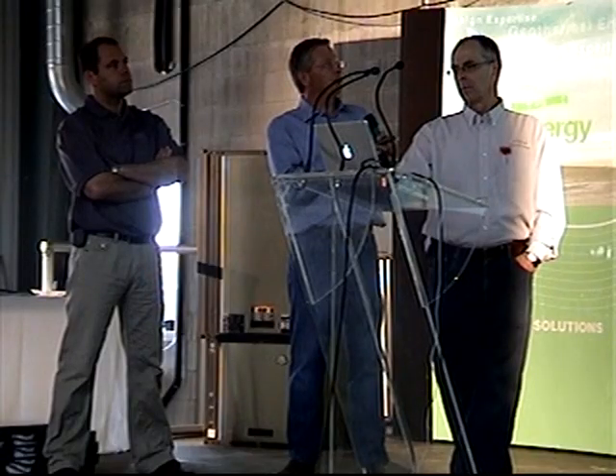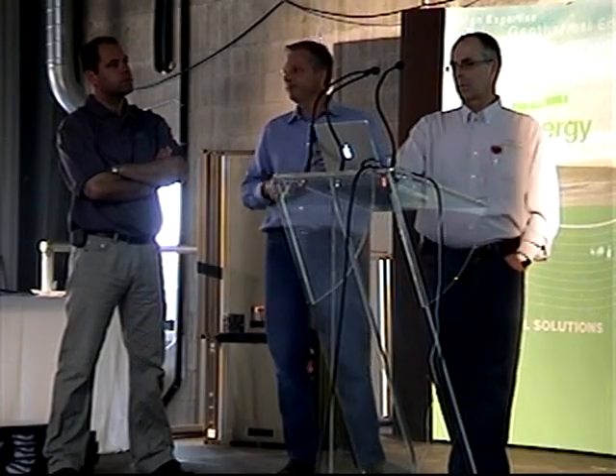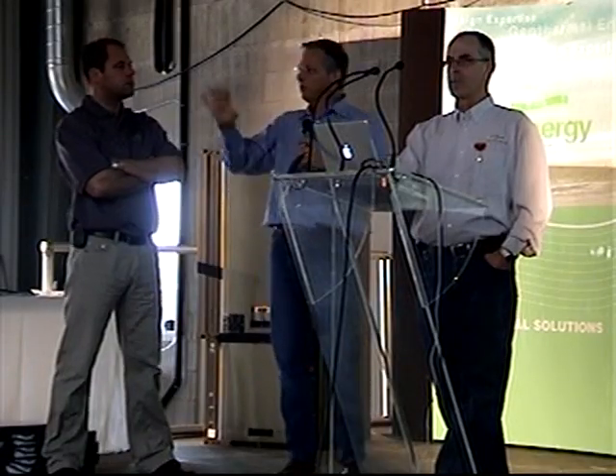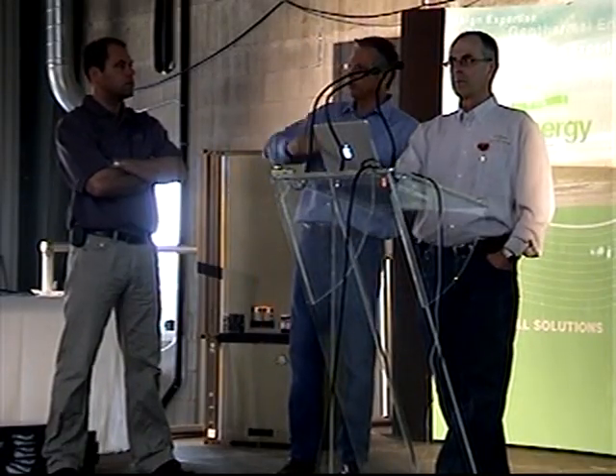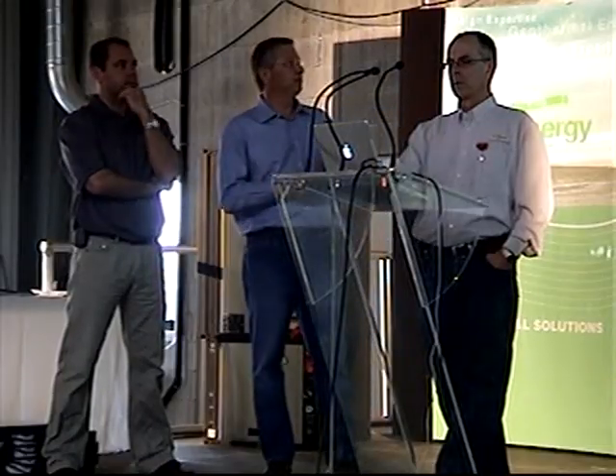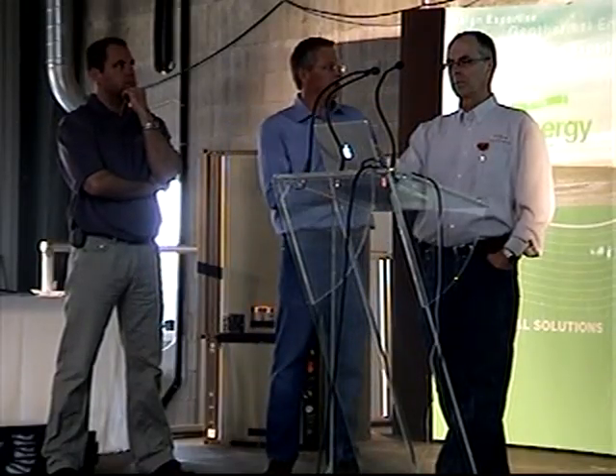There's your dip switch. You can turn off the unit performance sentinel. So if that thing is causing you any kind of grief with the homeowner, because you have an unusual system where what we think is abnormal is what you call normal, you can turn it off. And the next dip switch we use for two compressor units. So it puts a little delay between stage 1 and stage 2.